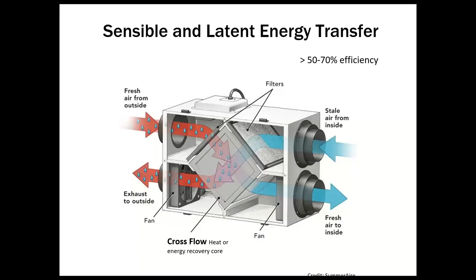But the concept here is good and illustrated in that, for instance, if we have warm, moist air outside on a summer day, and we are busily cooling and dehumidifying the interior air, we don't want to give away all of that effort by exhausting our cool, dry air and bringing in warm, moist air. And the ERV core helps us transfer the heat and the moisture to the outgoing stream. And it's important to note that the streams themselves do not cross-contaminate. They are side by side in counterflowing paths. And so the air does not mix, but the heat and the moisture can move.